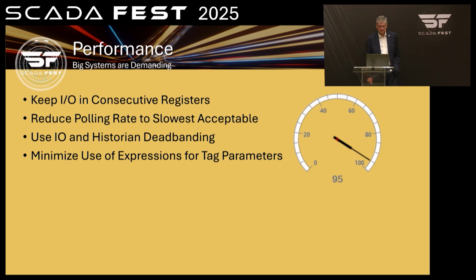Another one is expressions for tag parameters. Sometimes they're really, really useful, but don't get too attached to them and sprinkle them around like salt on your food. Because every time you put an expression in a tag parameter, it slows down the startup of the system. It has to evaluate, run some expression to try to figure out what that should be. There are lots of great cases where that's useful, but don't use them if you don't need to. Adding tag expressions to parameters can multiply your startup time by some significant multiple. You took a system that might run up in 2 minutes and suddenly it's 10.